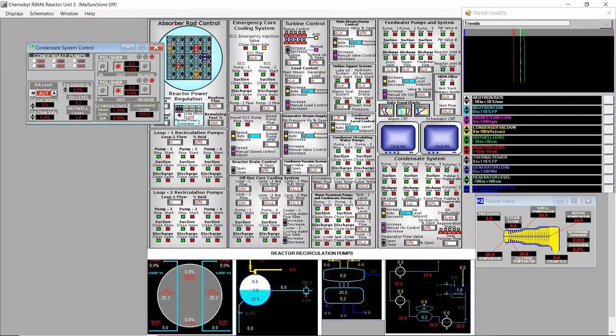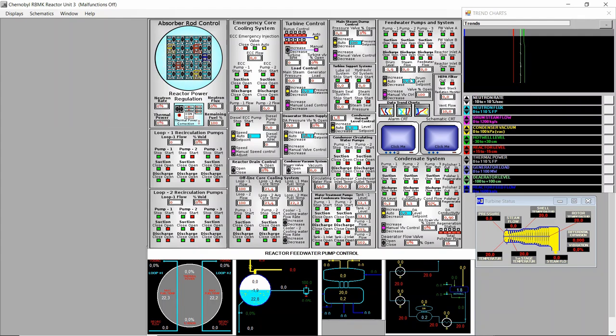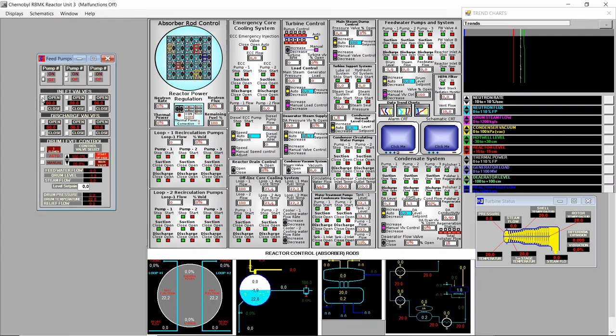We turn on the two polishers. Next, the feed water pumps and system — we will only turn on pump number one, so we need to open the inlet valve one. Once it's open, we turn on pump one, and once it's on we open the discharge valve. The drum level control is fine; it's in one-element control, it's on the startup valve, and everything else is fine.